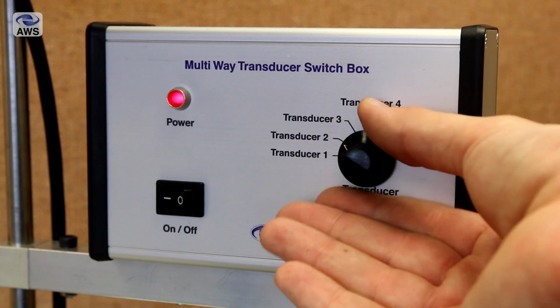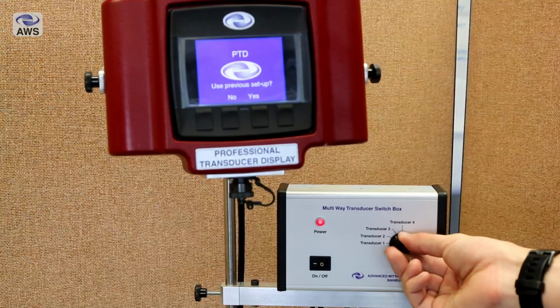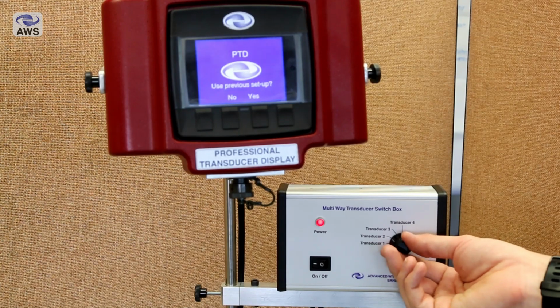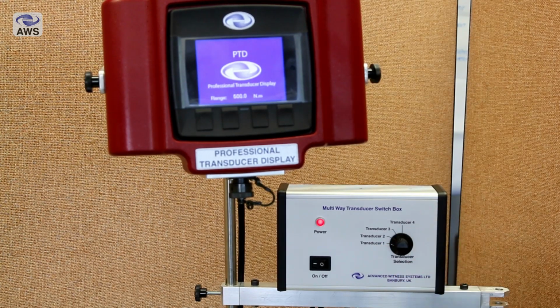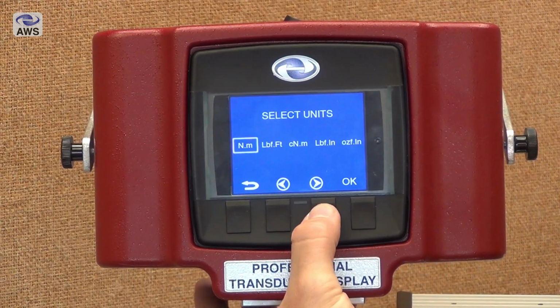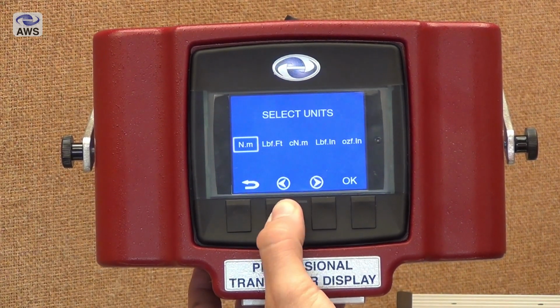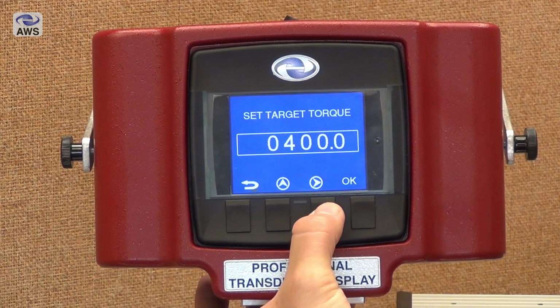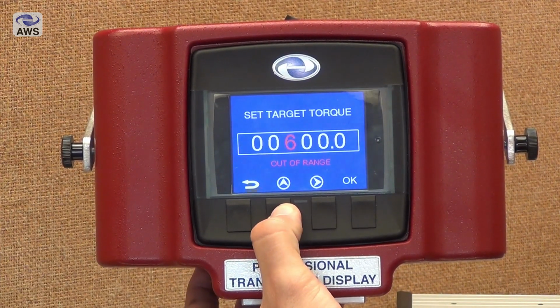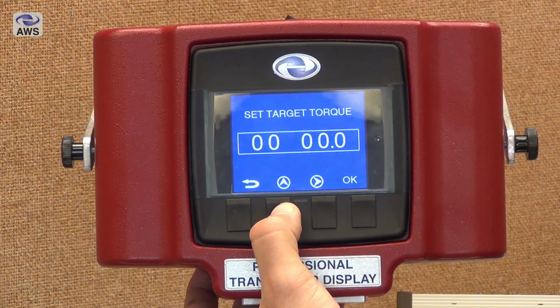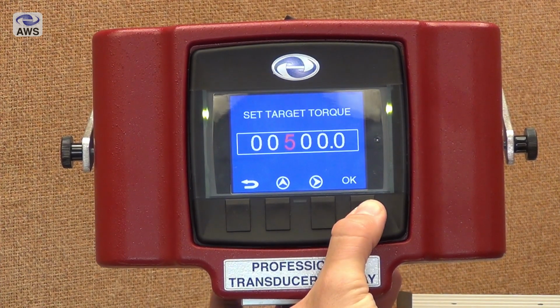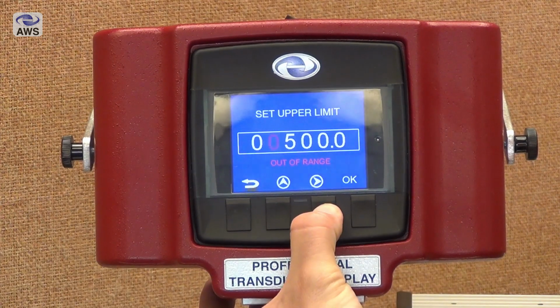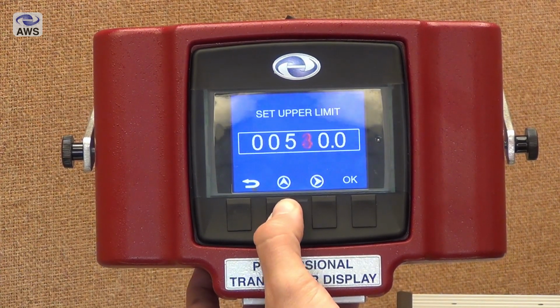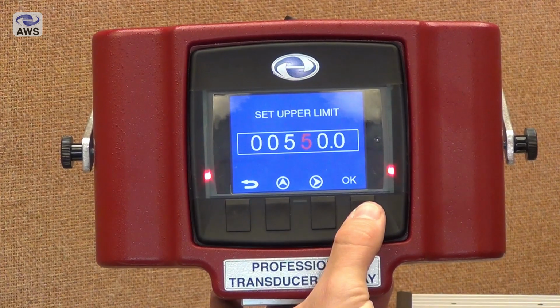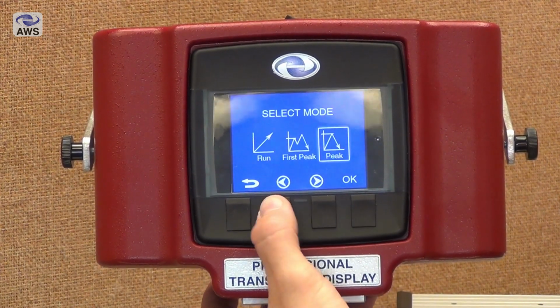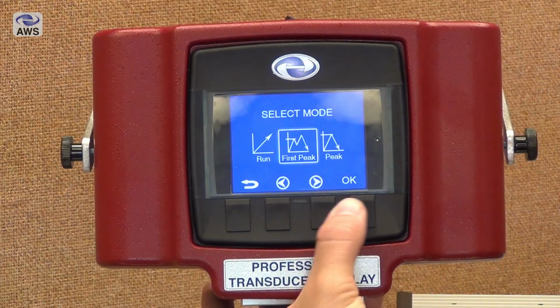Select the transducer using the transducer switch box. The display will automatically detect the selected transducer and the switch box keeps all attached transducers powered for temperature stability. Using the soft buttons on the front of the display, follow the on-screen setup. Firstly selecting the units and then the target torque. This is the torque that the wrench is set to. Then set the upper limit. This is the limit at which the machine will stop if reached, so this is a safety limit. Then select the mode, first peak for click types and peak for cam and dial types.